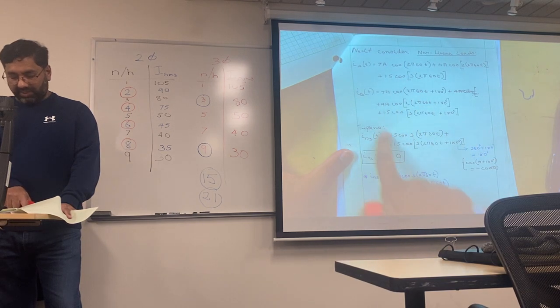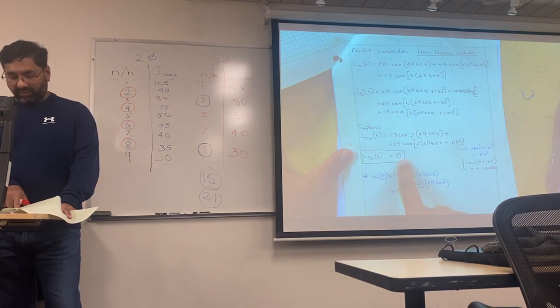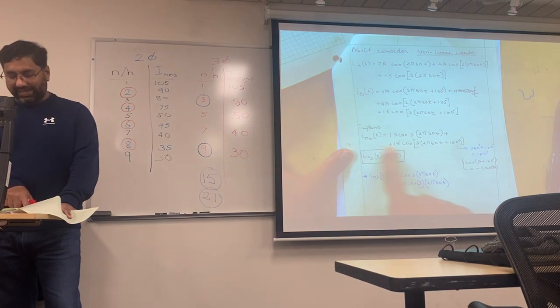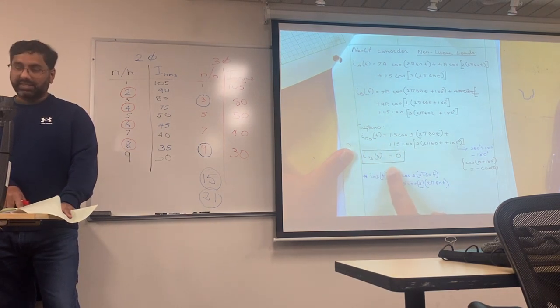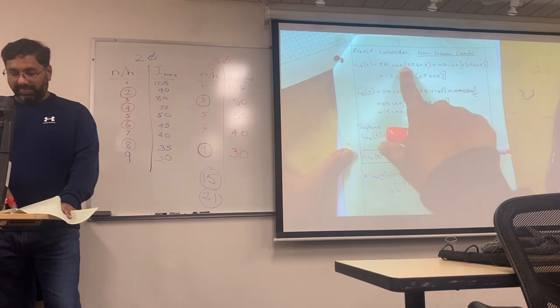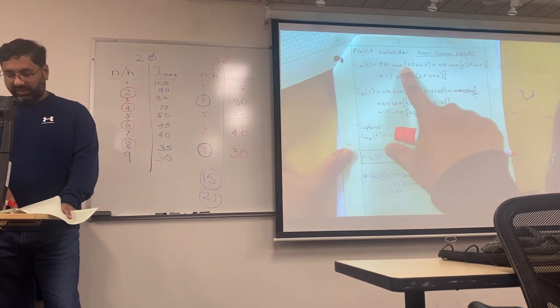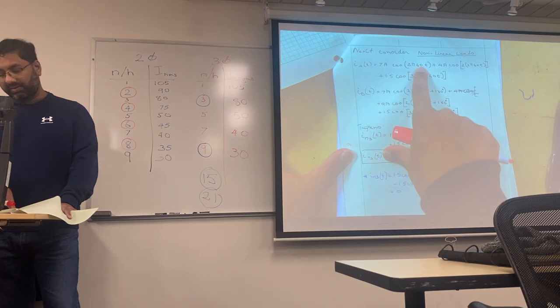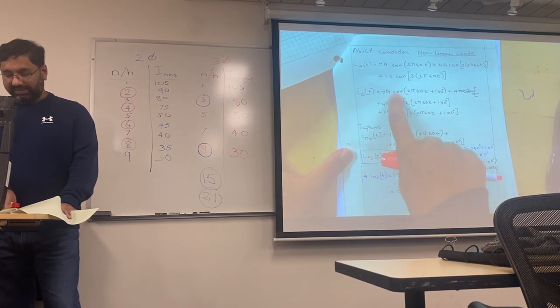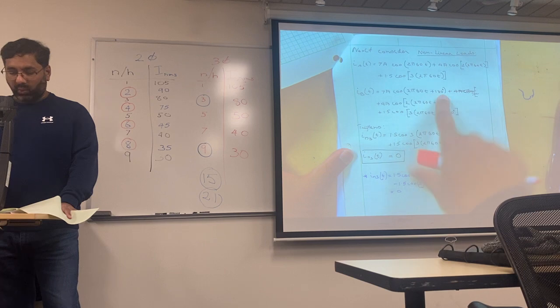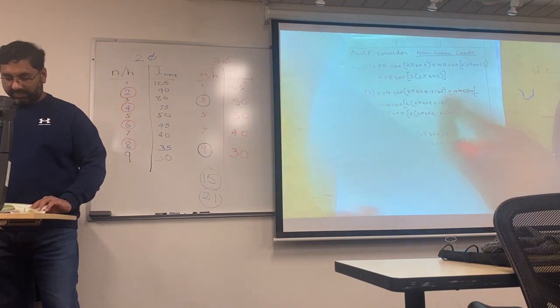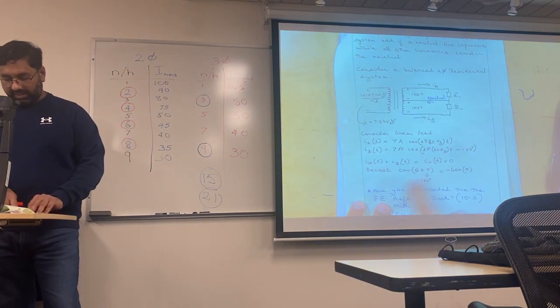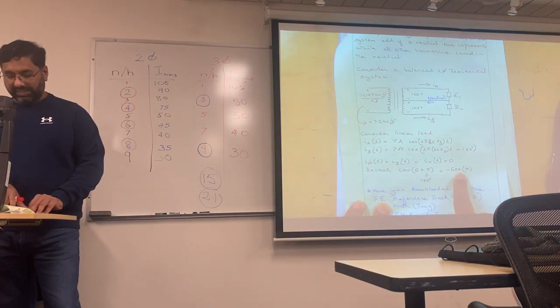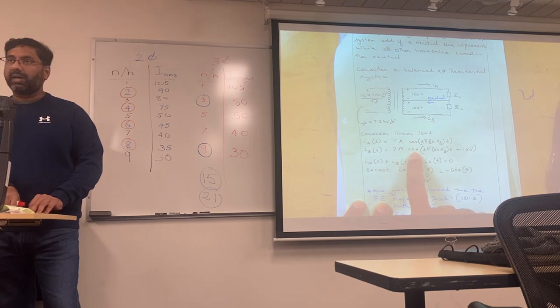When I looked at the neutral, the third ones, the odd ones, so 3, 6, 9, all of them are cancelling out in a 2-phase. Similarly, the first harmonic, that is 7A cosine 60 hertz and 7A cosine 60 hertz plus 180, is cancelling out because of this trig ID: cosine of theta plus pi is negative cosine theta. That means the first one and the second one are just cancelling themselves out in the neutral.